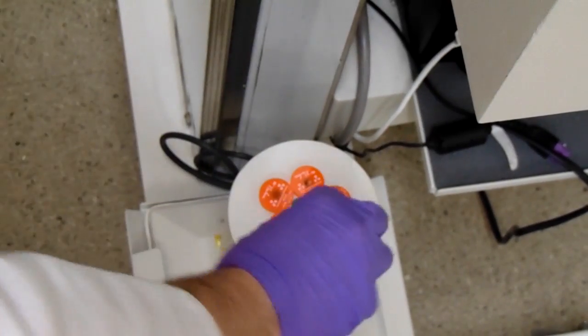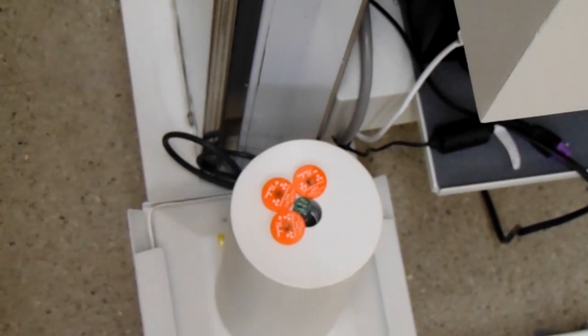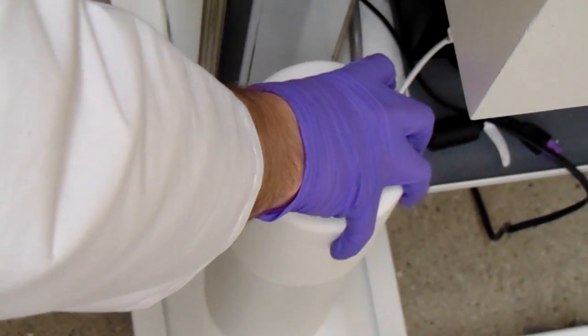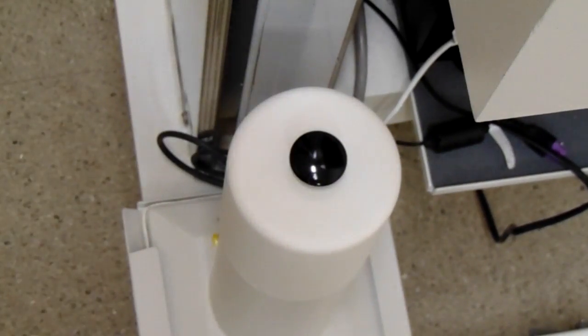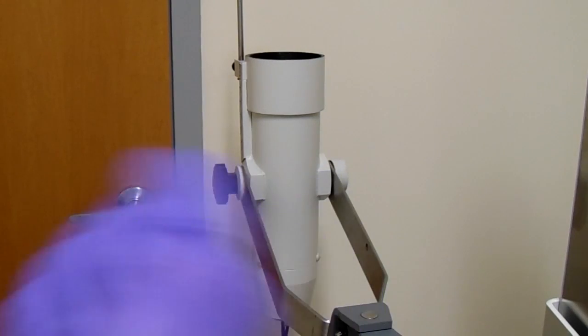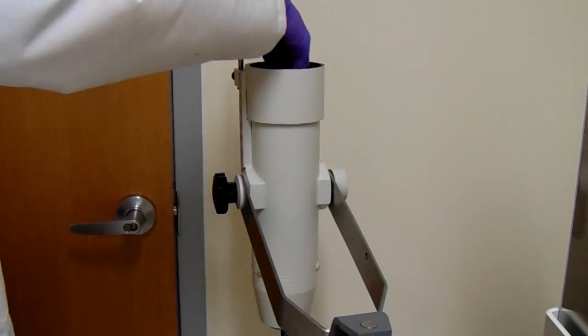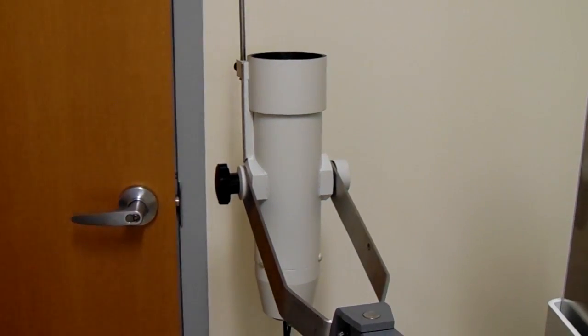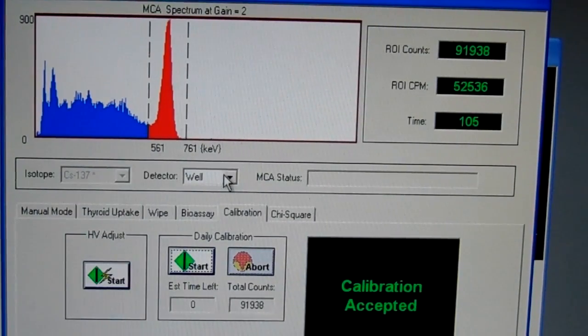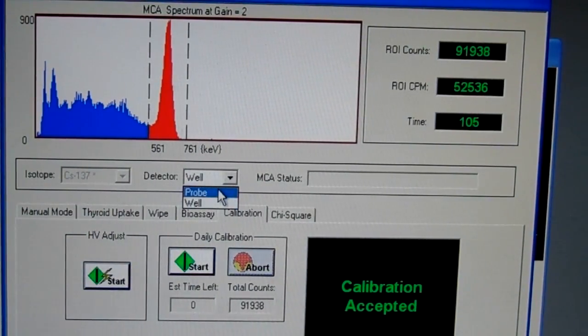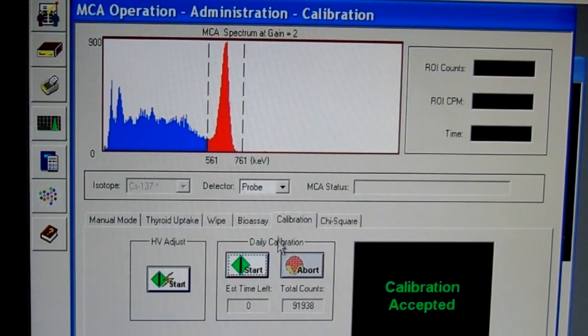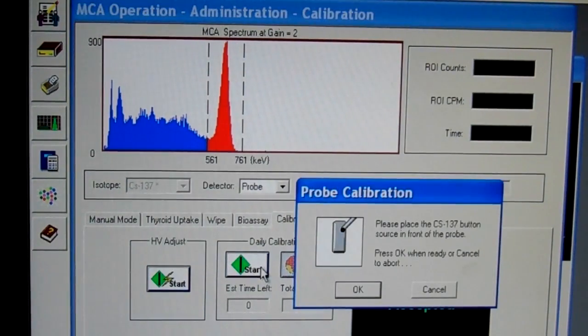Now after that, you're going to take the lid off your well, grab 2 of the discs from your cesium disc sources, and then we're going to use these 2 discs to do constancy on our probe. Now we take the 2 discs and we lightly place them into the bottom of the probe so that we don't break the discs, and then we go to the drop down menu on the calibration tab and go to probe, and then hit start just like we did for the well.